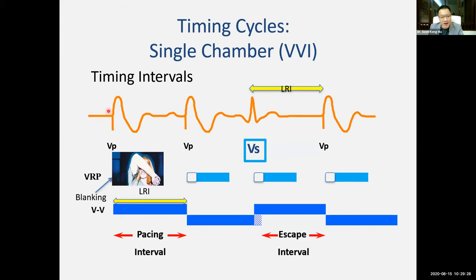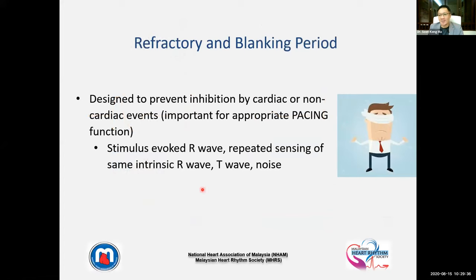And then after that, there is a refractory period. Now why do we have a refractory period here? Simply because you want to prevent inhibition by cardiac or non-cardiac events. Because if you deliver a pacing spike, there'll be a saturation of the sensor and there'll be decay in the signal. And for that period of time, the sensor may still be able to detect its own pacing spike, so to say, stimulus evoked R wave, this is a term for that.